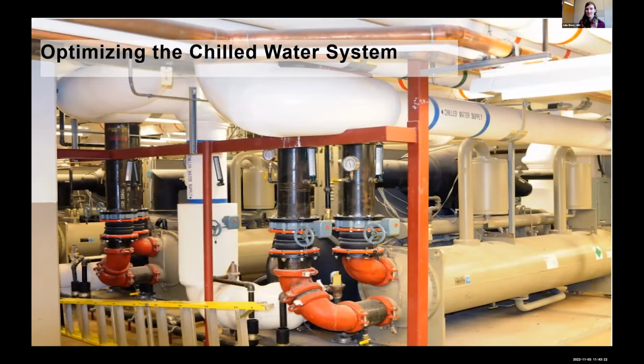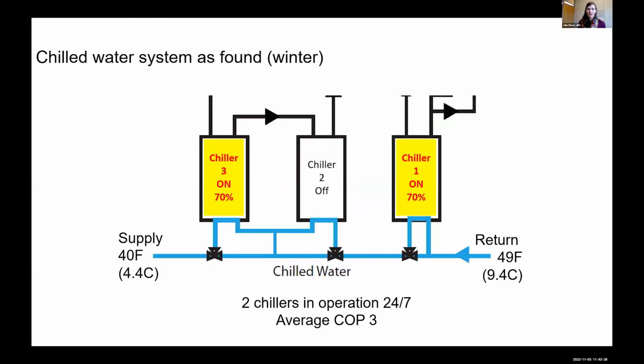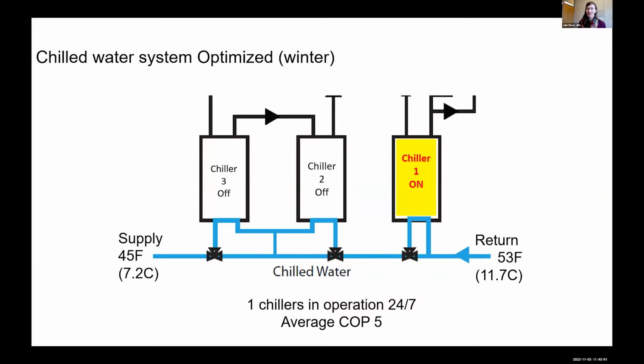Next, looking at the chilled water system. We found it had 2 chillers operating most of the time with an average COP of 3 and a fairly low supply water temperature, roughly 4 degrees Celsius or 40 Fahrenheit for you people in the imperial system, and return of 49. What we were able to do was increase that supply water temperature from 4 to 7, and then it also increased the return, and it increased the COP of the chiller from 3 to 5. As a result of that, only one chiller had to run rather than 2.